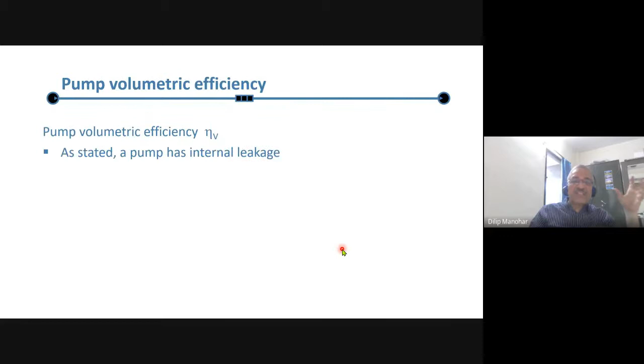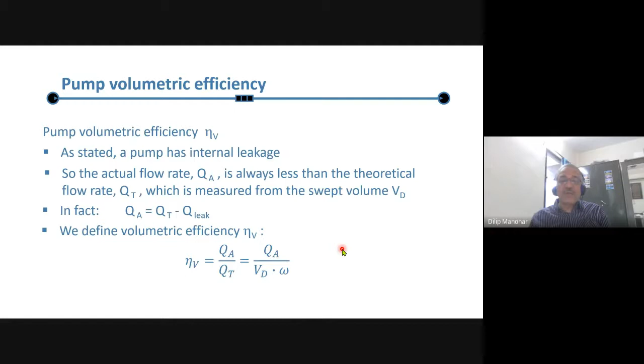What is the volumetric efficiency we are studying now? Volumetric efficiency accounts for internal leakage. The actual flow rate QA is less than the theoretical flow rate QT, which is the swept volume Vd times omega. In fact, QA is QT minus Q leak: the theoretical flow rate minus the leakage flow rate is the actual flow rate. So we define the volumetric efficiency of the pump as eta V equal to QA upon QT, that is QA upon Vd times omega.